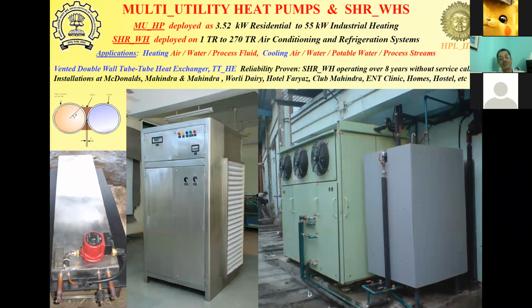Now, the condenser heat in this case is used for heating cleaning solution in an automotive factory. The cleaning solution could be replaced with water for your hostel application. So if you imagine keeping this inside your mess, this will take the indoor air from the mess, cool the air, dehumidify it, and release it back into the mess. And the heat taken from that, plus the power consumed by the compressor, will be delivered as hot water, which can supply hot water for your bathing, dishwashing, and various other applications for washing machines and other things. So this unit can do two things in this form.